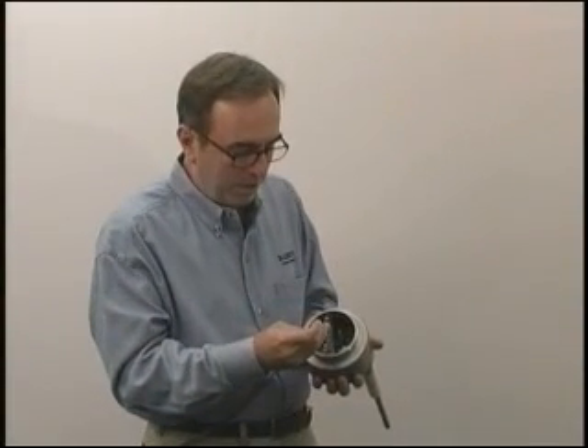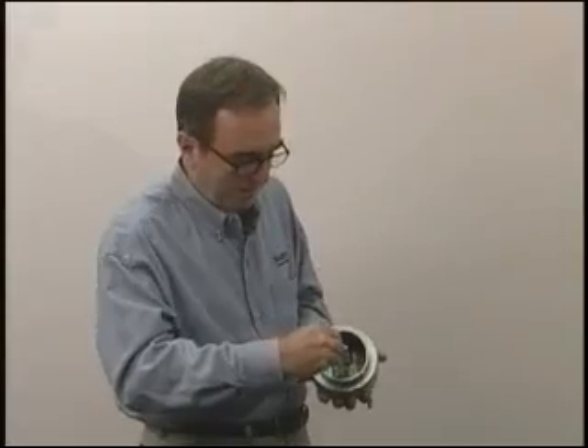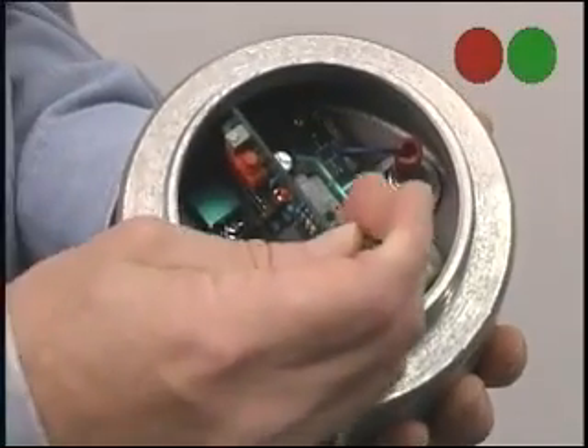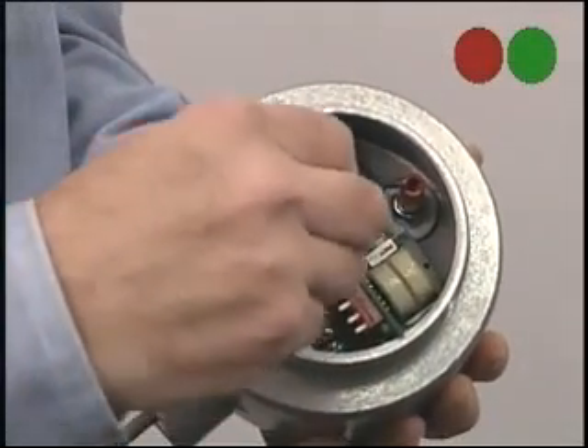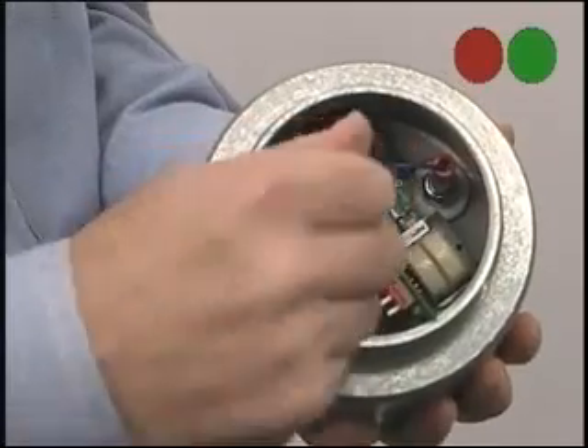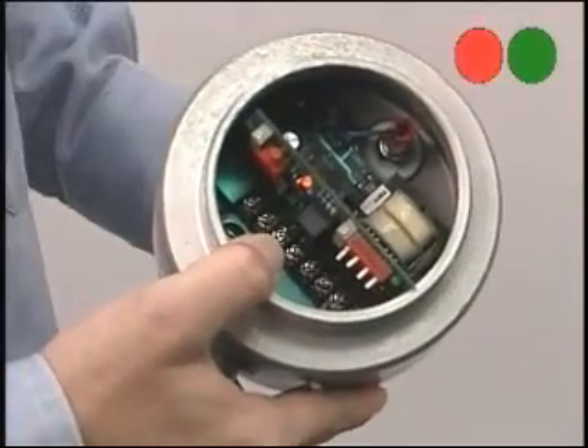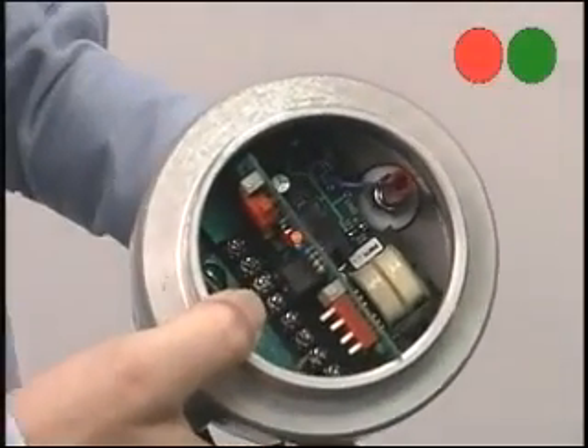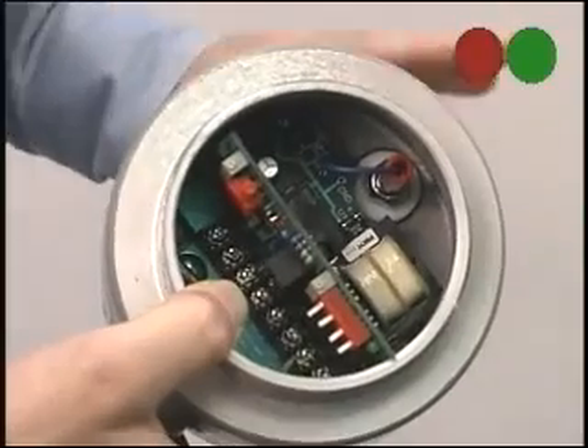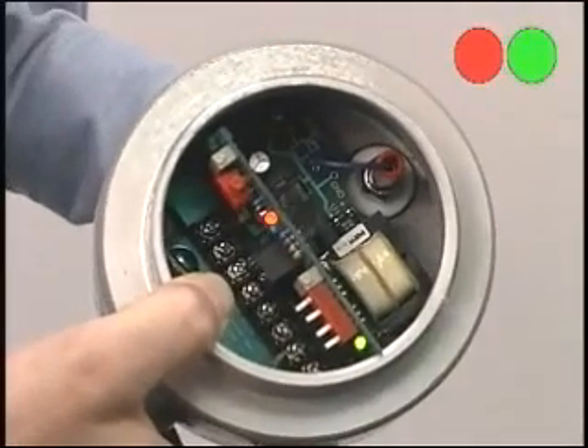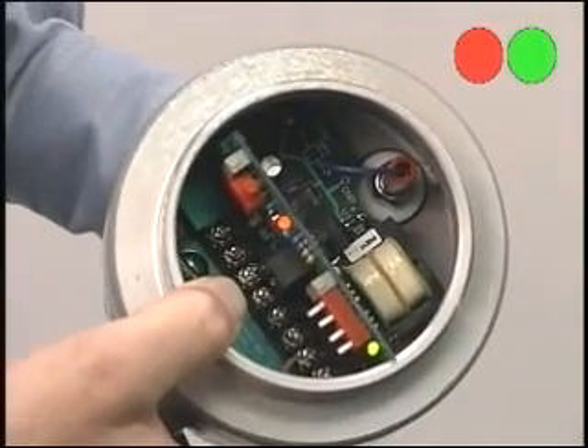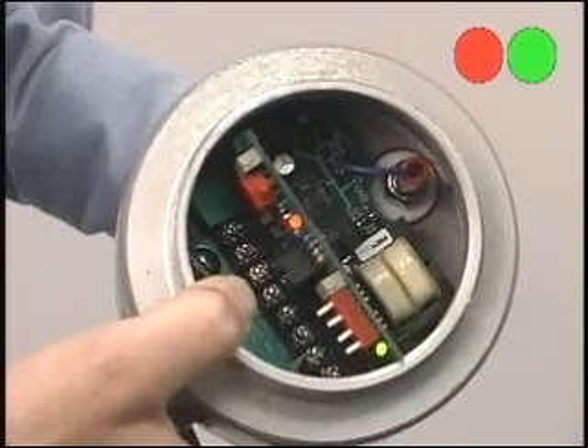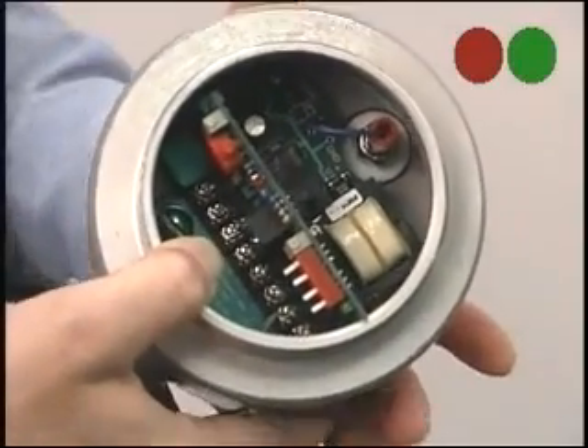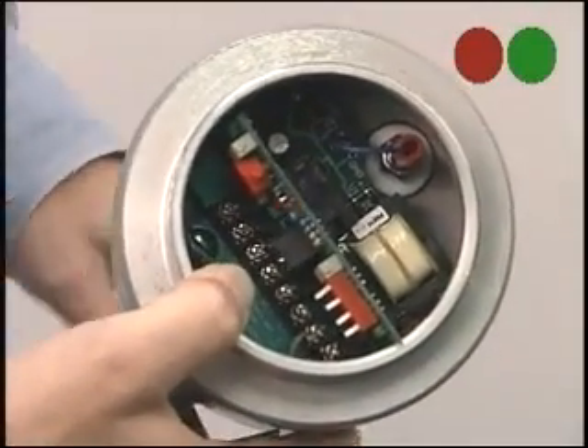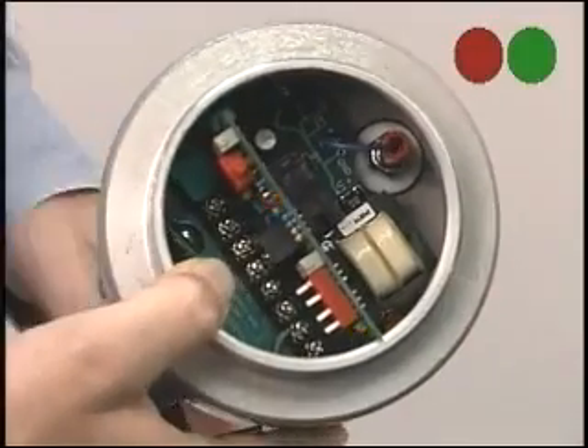The last thing I want to show you is a time delay adjustment. I'll put a little time delay on this by turning the time delay potentiometer clockwise. Now you can see the red LED is coming off and on, but the green LED is not actuating, and it won't until the level has been there for a certain period of time. This is adjustable from 1/8 of a second to 2 hours. This would be used typically to ignore a wave or a splashing action in the tank.